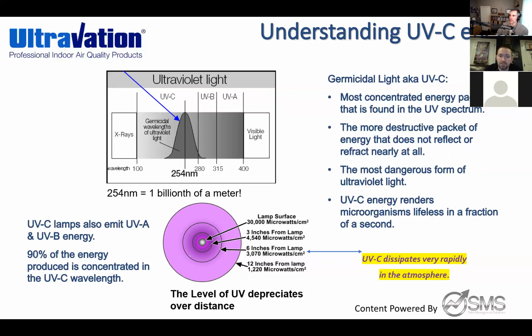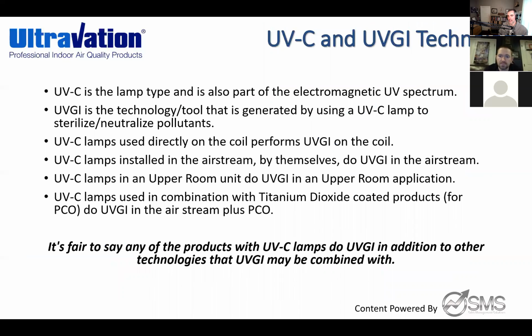So to sum up that slide: UVC is the most dangerous wavelength, and it's what's going to kill things. That's why, whenever you're on a job or someone asks about the understanding of UVC versus UVGI, remember UVGI is basically impossible unless you have a UVC-class wavelength bulb per the ASHRAE guidelines. If you're installing a UVA or UVB bulb, those are different wavelengths, and you're not doing the job. Any products you look at must be a UVC wavelength lamp.